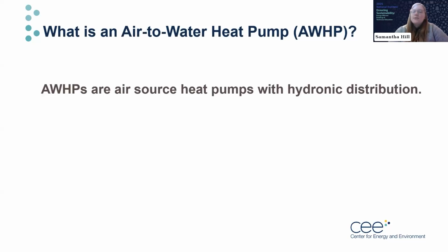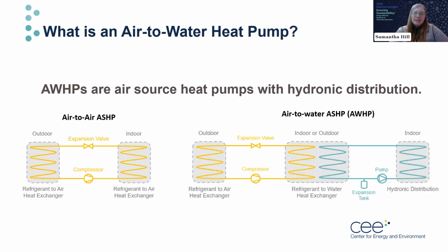Air-to-water heat pumps are air source heat pumps with hydronic distribution. So they're very similar to air source heat pumps, if you're familiar with those. They just distribute the heat through hydronics instead of an air distribution system. To look at this a little bit more closely in a schematic view, here's an example of a very simplified air source heat pump schematic. On the left-hand side, you have an outdoor heat exchanger moving heat into a refrigerant, and then you have an indoor heat exchanger moving heat from the refrigerant to the air in that indoor space.